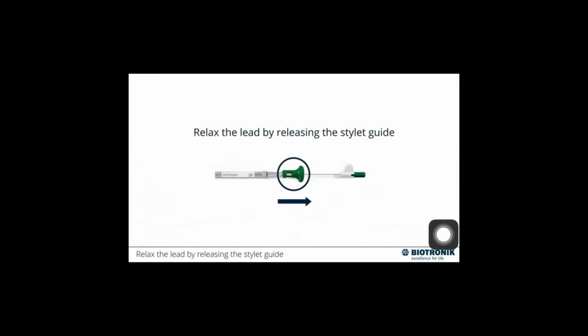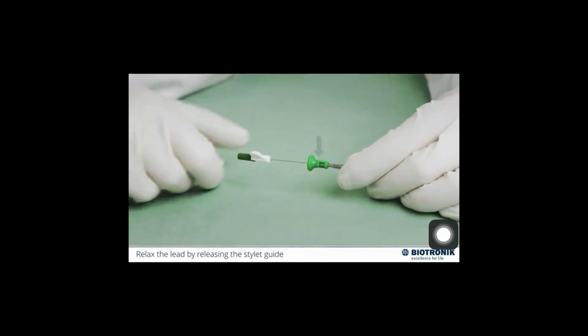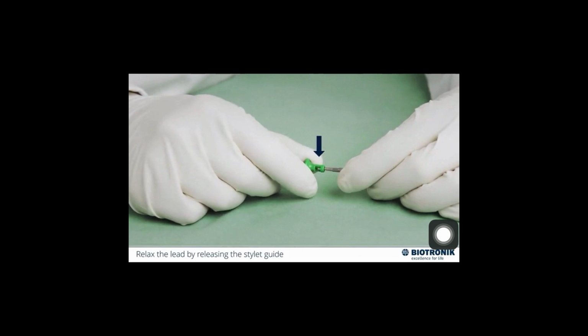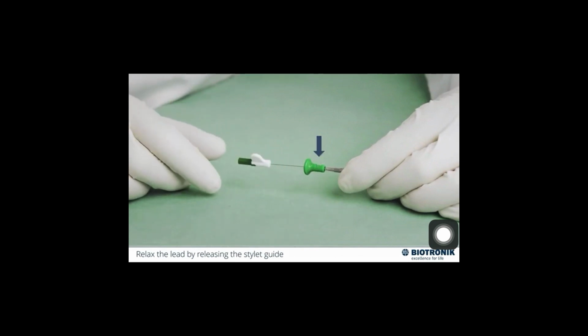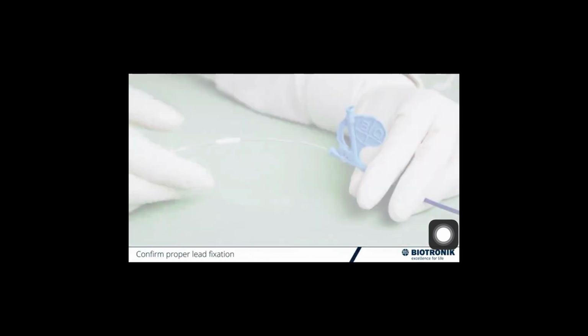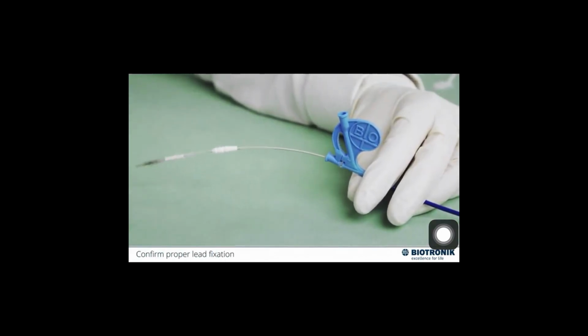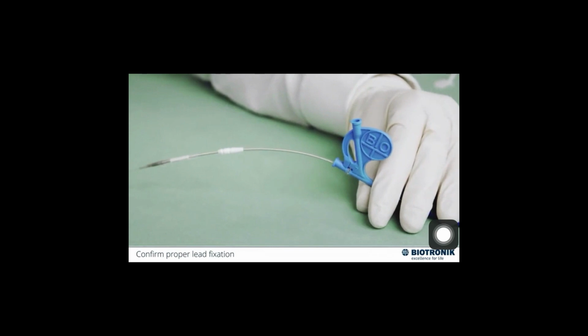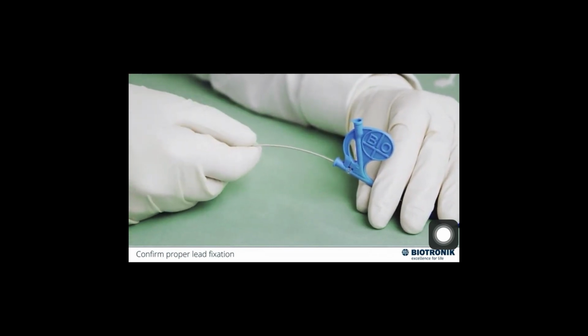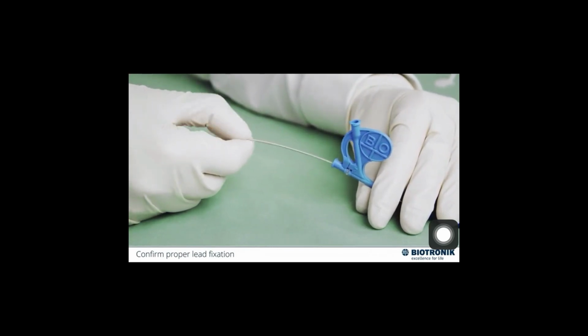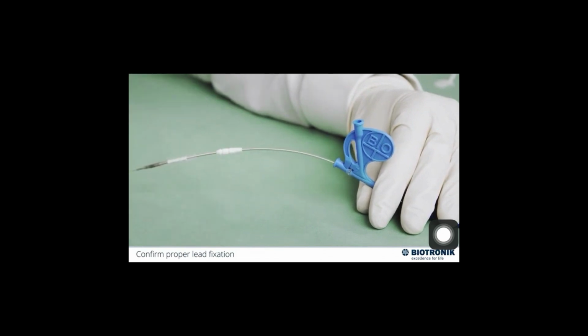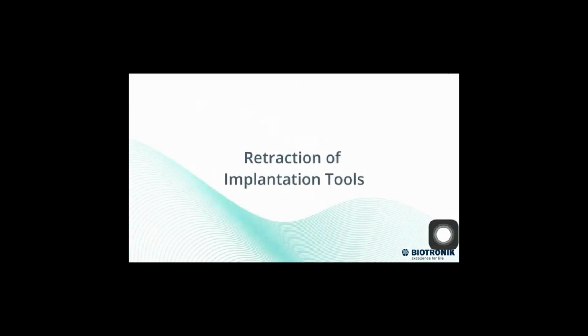Once the lead is successfully placed and fixated, carefully release the green stylet guide. If the stylet guide turns several times once it has been released, you can be sure that tension was built up successfully within the lead body during this procedure. While observing on fluoro, perform a suitable maneuver such as a gentle tug test by pulling on the lead to confirm that it is fixated in the tissue.